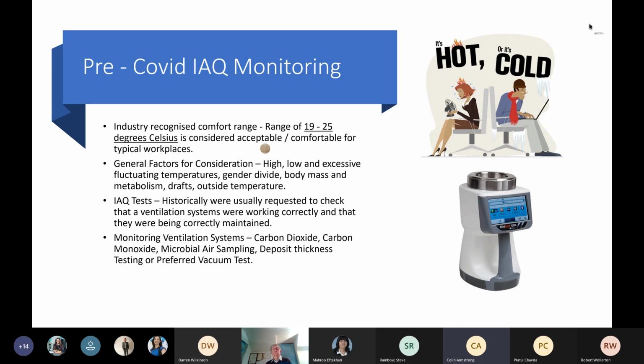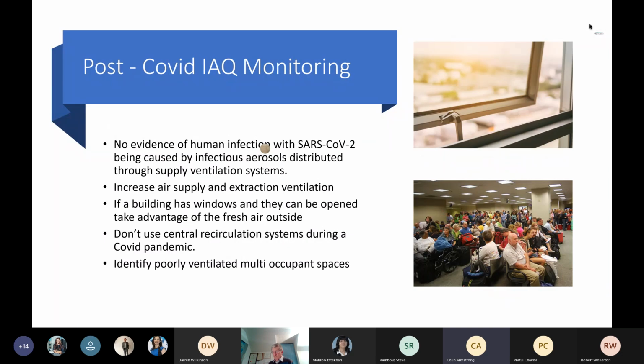Ideally 50 centimetres away from soft furnishings and tables or anything that could put an influence on that pump drawing the air in. And then a second set of samples should be taken close to the ceiling, but not in direct airstream from a grill or diffuser. The sampler should be at arm's length. And that's generally what people asked us to do before COVID came out, and that's slowly changed to now post COVID.